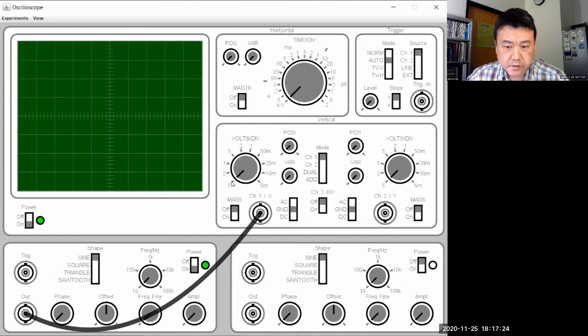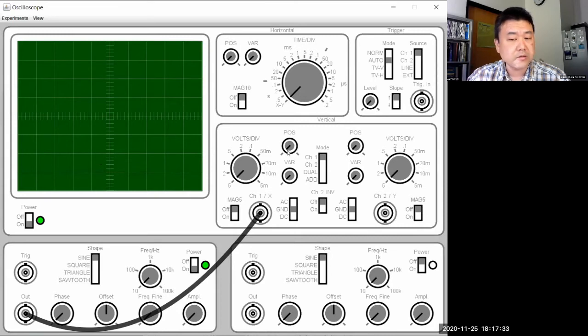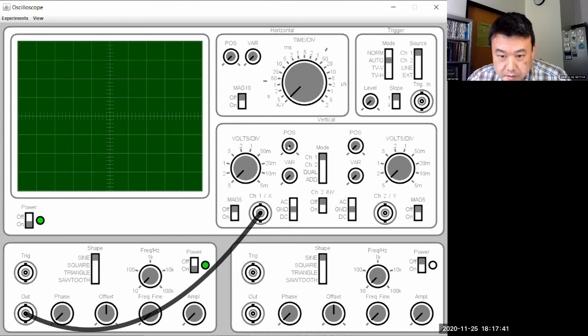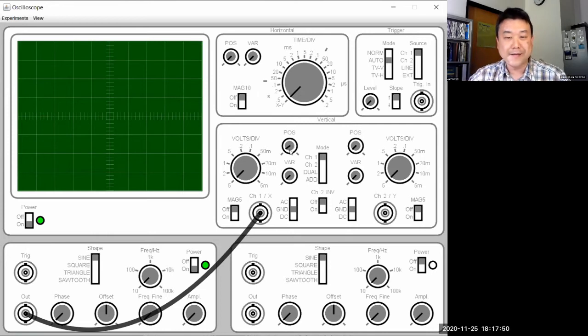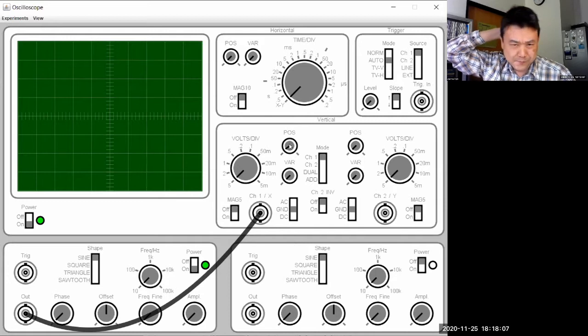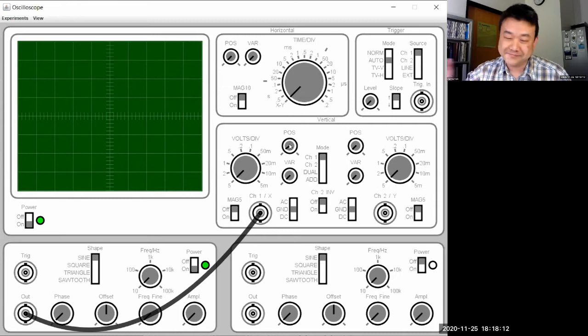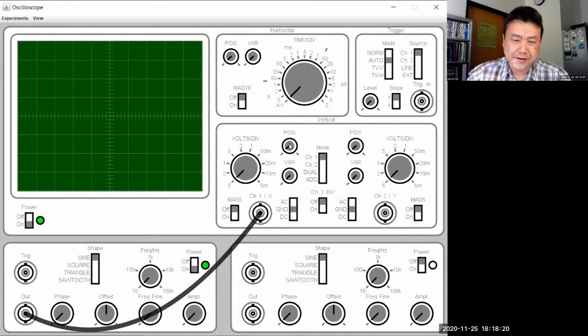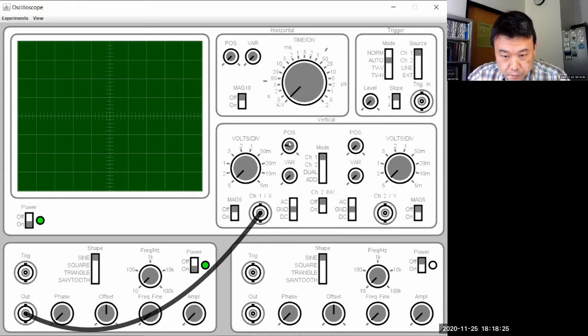The volts-per-division is at maximum — that's probably fine. But this position knob, which I'd guess controls the vertical position of the signal, is turned all the way counterclockwise. It should probably be somewhere in the middle. Clicking and dragging does nothing; left-clicking does nothing. If I right-click, you might see it move very imperceptibly. If you read the instructions on the web page, it says the mouse scroll also controls it. So in tech world there's the acronym RTFM — read the fine manual — and the oscilloscope is one of those devices where you really have to read the manual, even for the simulation.